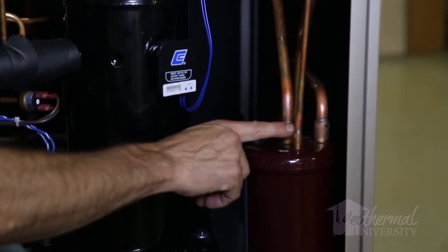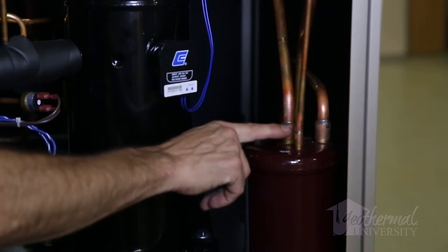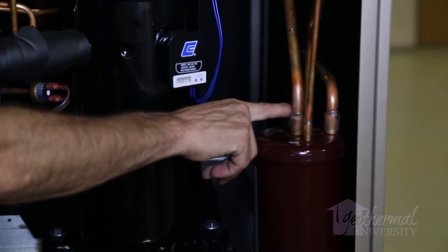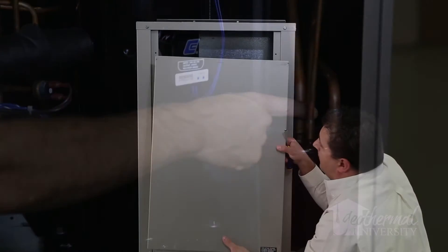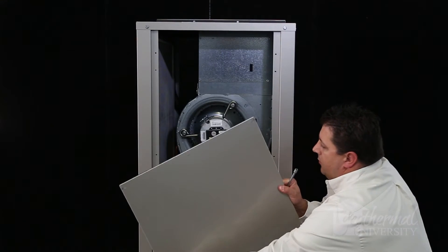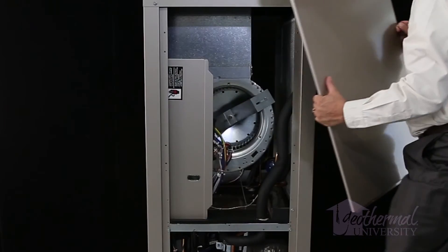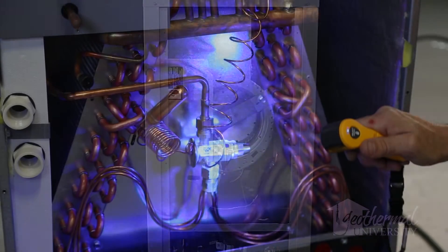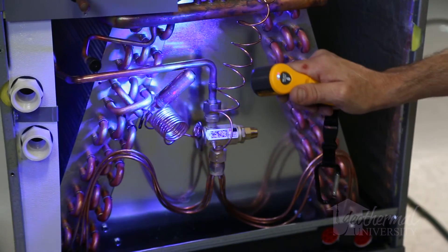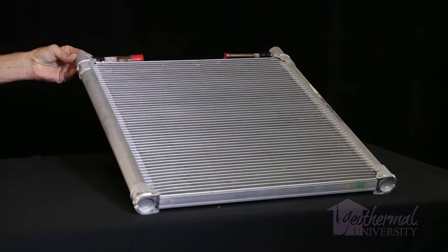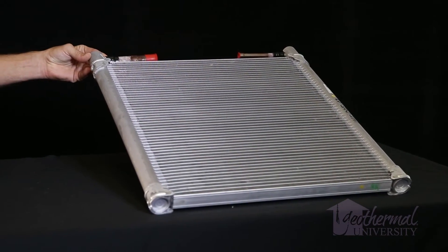It may take many months, even years, of unit operation to cause enough oil blow off to accumulate on the outer side. Because evaporator sections are cabinet contained or framed into areas that do not allow easy access, evaporator coil leaks are difficult to locate. Experience has taught us to search smart when looking for leaks.